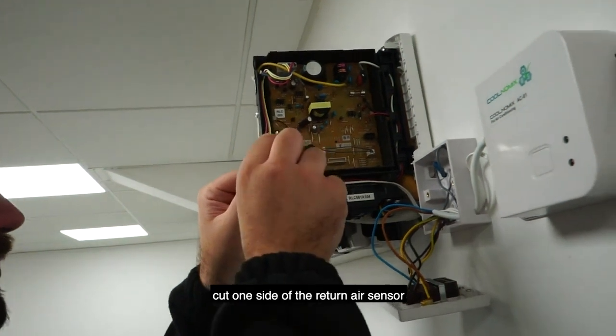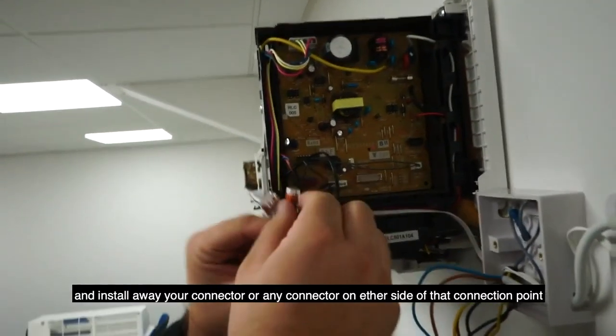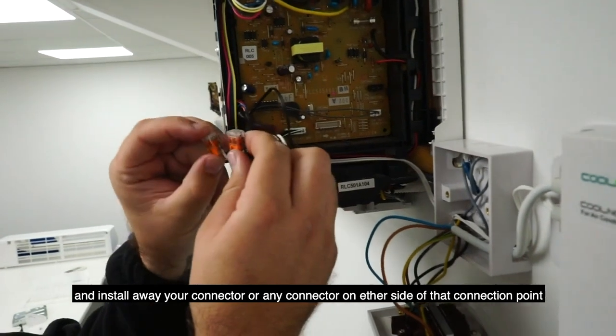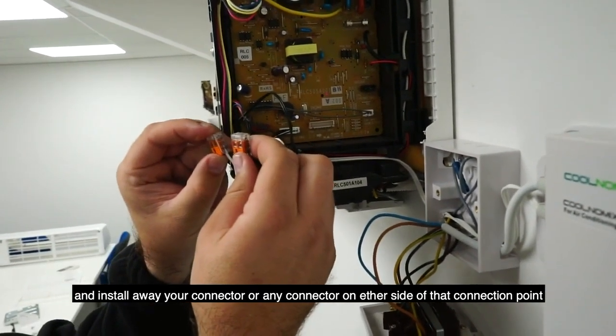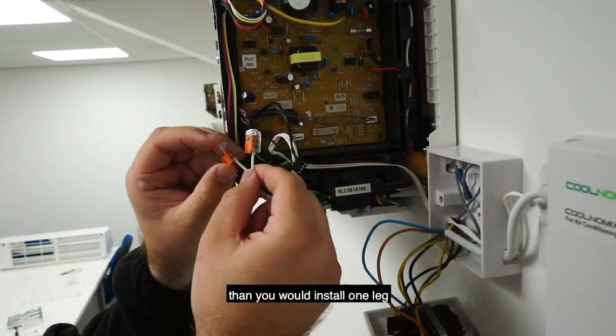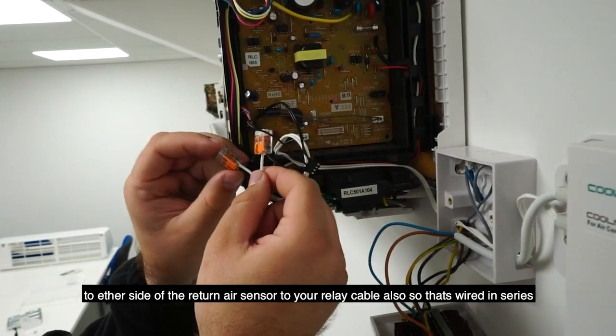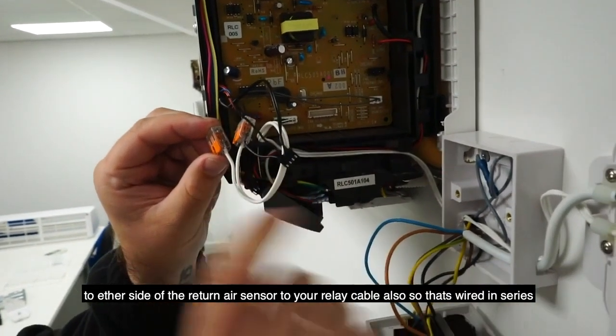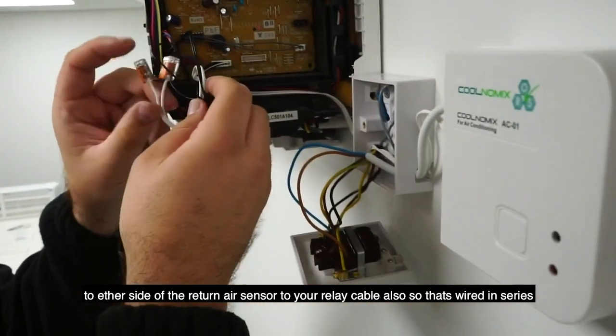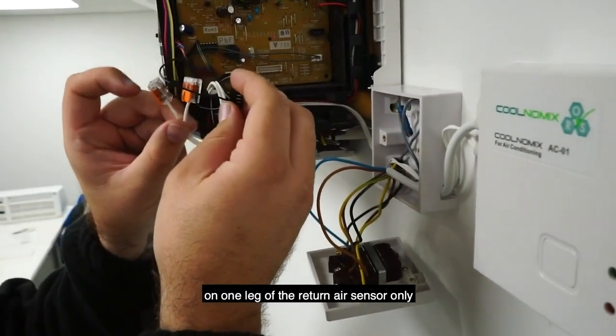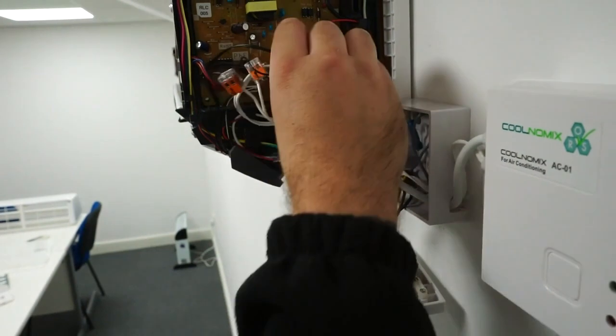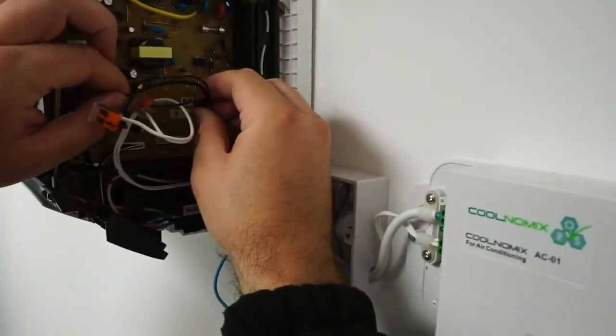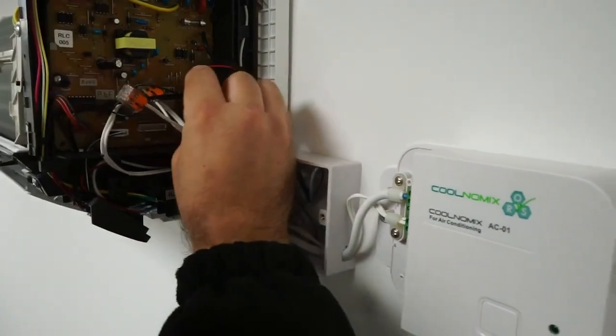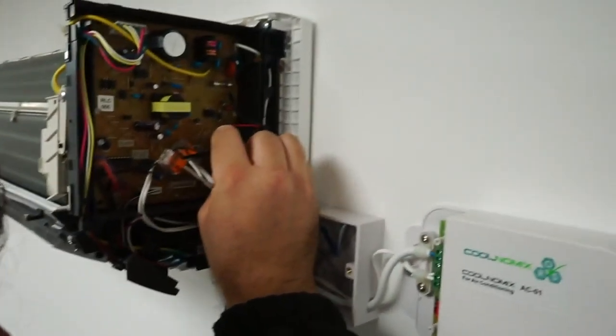Cut one side of the return air sensor and install a Wago connector or any connector on either side of that connection point. Then you would install one leg to either side of the return air sensor to your relay cable also. So that's wired in series on one leg of the return air sensor only. Then plug back in the sensor onto the PCB board.